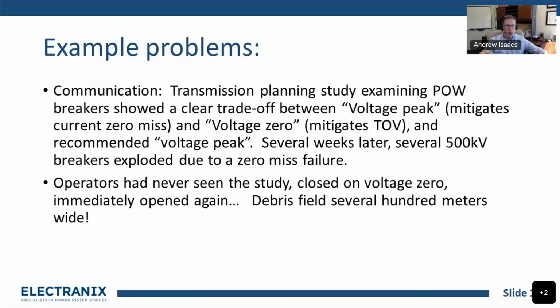If you can hit it on the voltage peak, you might minimize the potential for a current zero miss, making sure your current is close to a zero crossing. And on a voltage zero, you're likely to mitigate transient voltages that end up on the circuit and maybe protect your arrestors.